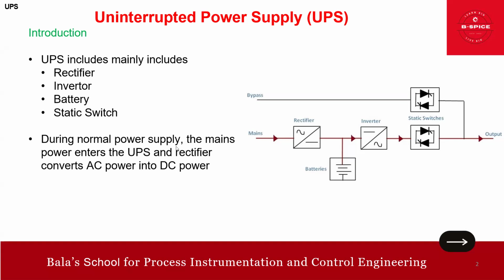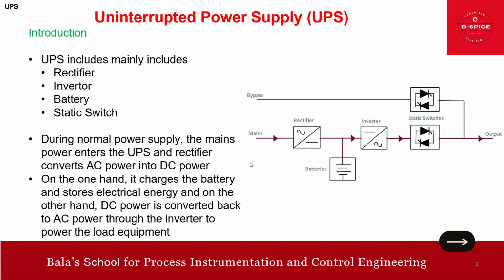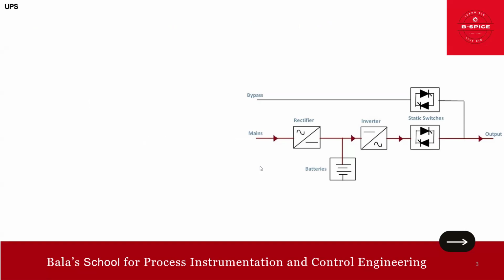During normal power supply, the mains power enters the UPS and the rectifier converts the AC power into DC power. On one hand, it charges the battery and stores the electrical energy. On the other hand, the DC power is converted back to AC power through the inverter to power the load equipment. That is what is happening inside.